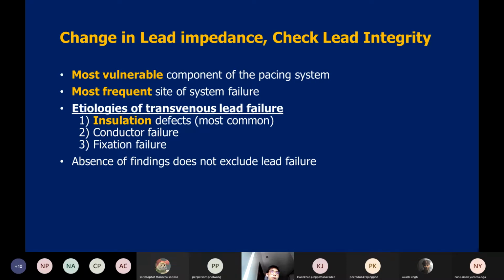I had a patient with a high impedance, and I checked through the chest X-ray. There was nothing wrong. I checked other functions like pacing and sensing function. There was nothing wrong also. But 2 or 3 months later, it came up that the insulator was broken and the pacing threshold was going up after that. So if there is something wrong with the lead impedance but you cannot identify any problem, you have to follow up patients sooner than the regular follow-up.